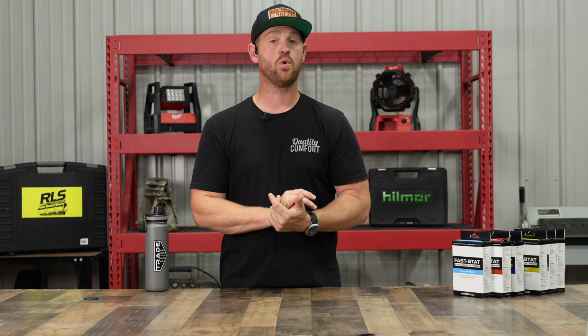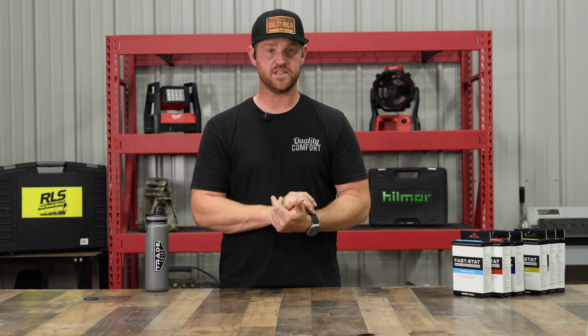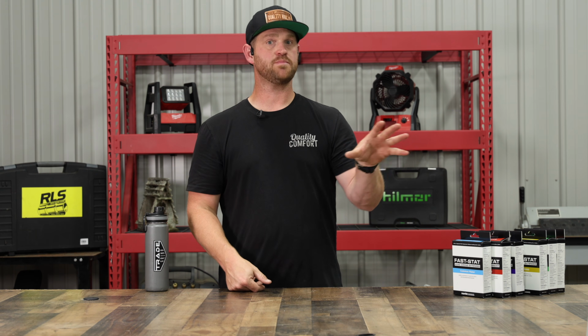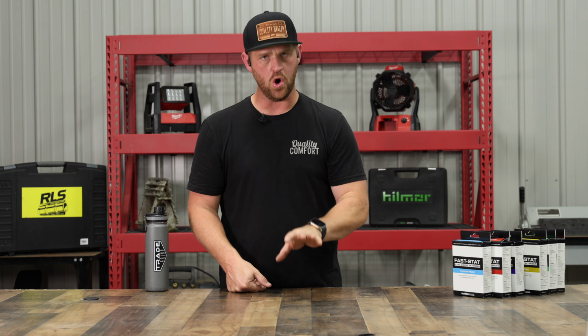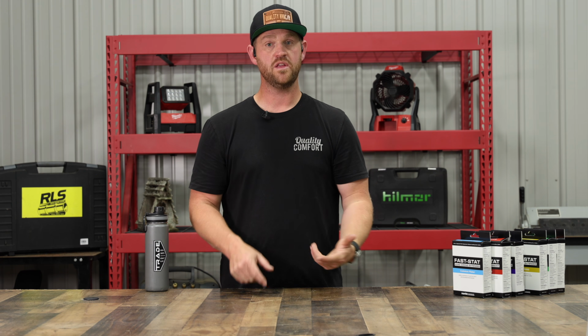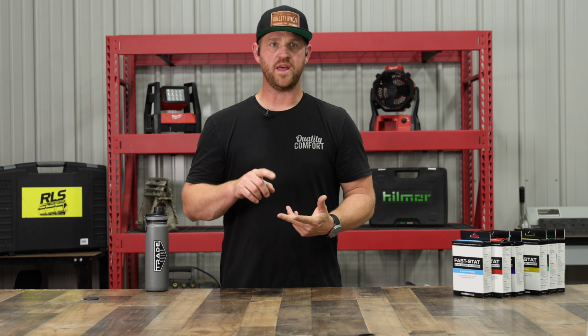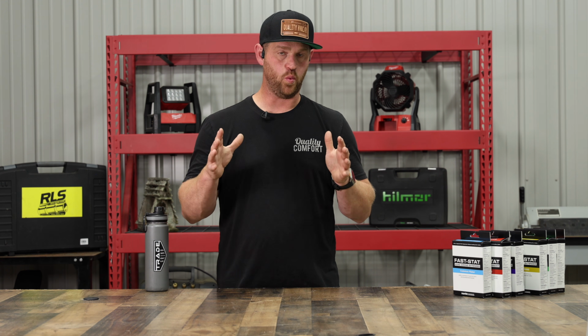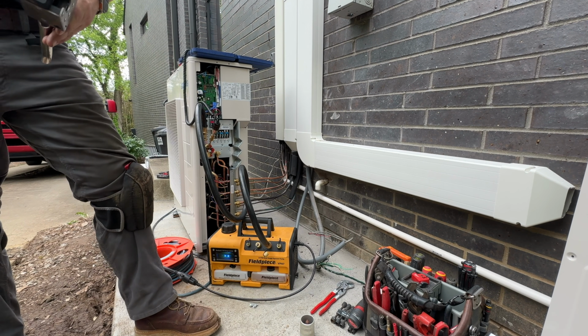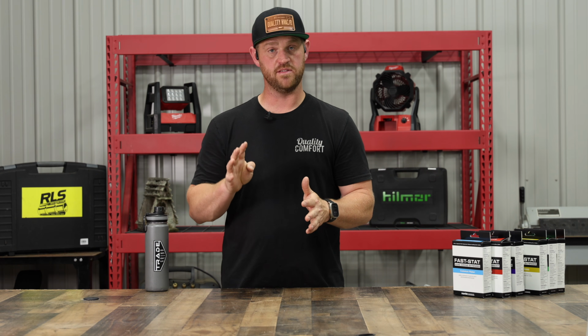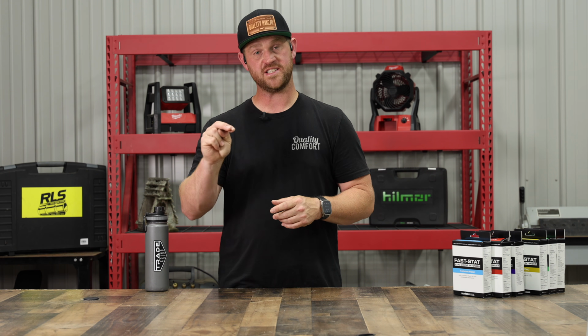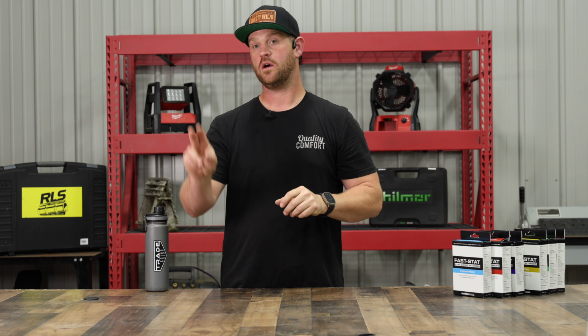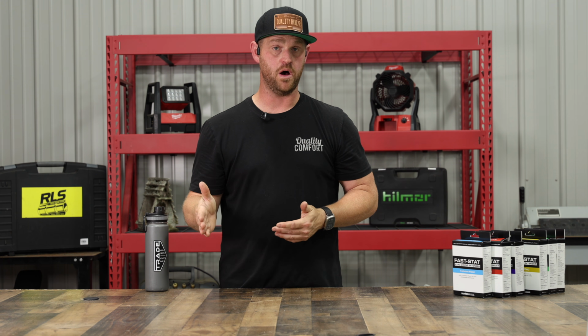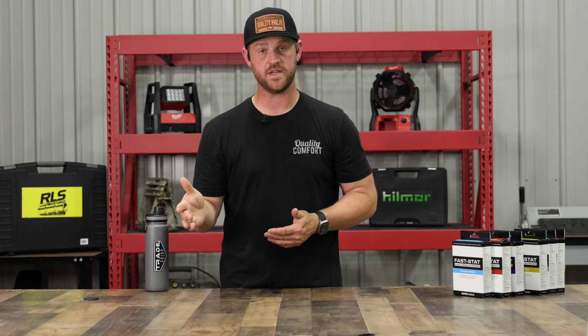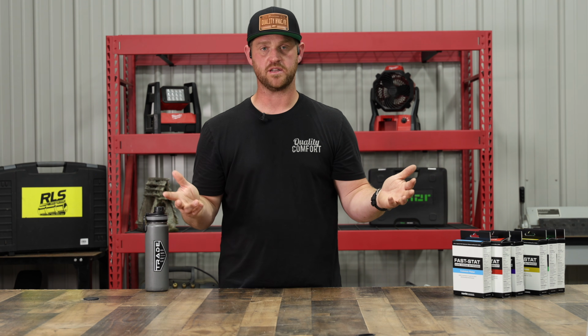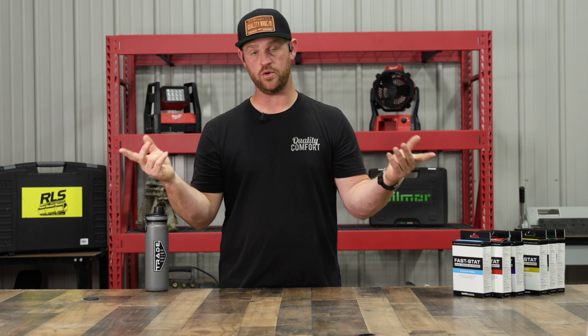Those things are way more in depth than a traditional, let's say, multi-port variable speed. We talked about variable speed, but we didn't actually talk about multi-zone variable speed, because that's when you get into the VRF type of equipment. They also have multi-port. So you have one condenser outside, but then you have, let's say, 3 or even 4 sets of line sets. They go in. So each port or each set of line set will go into one indoor unit. So basically, if it's a 4-pipe system or 4-port system, you're going to have 4 indoor units. That's basically how that works. If you have a 2-port system, you have 2 indoor units, and so on.